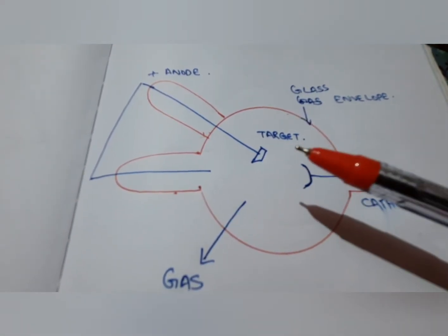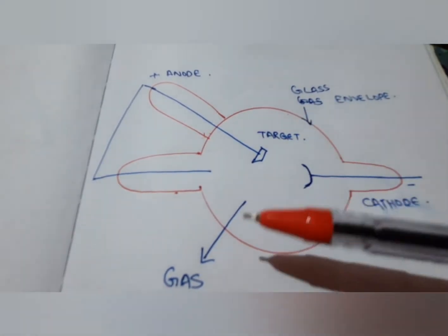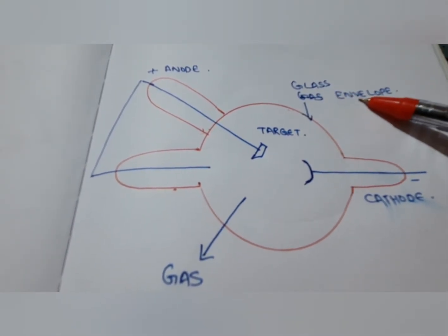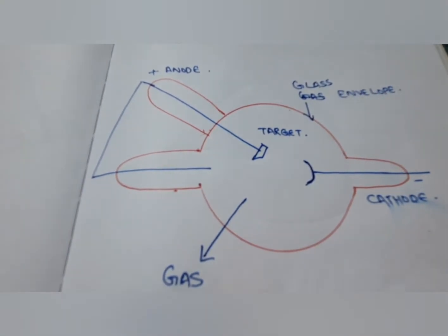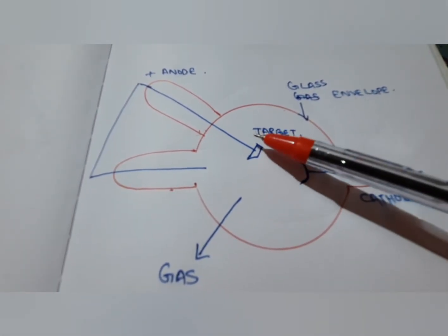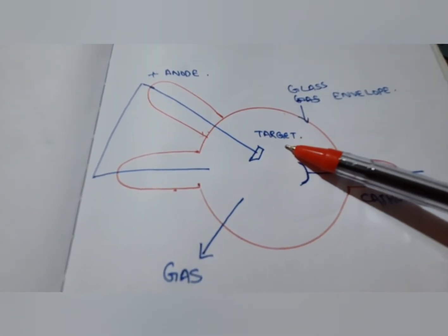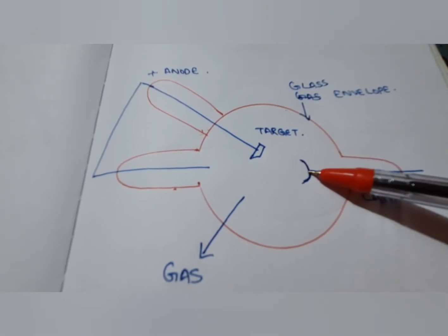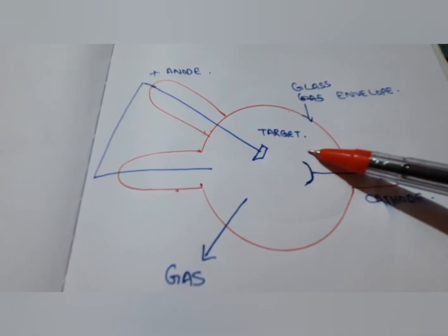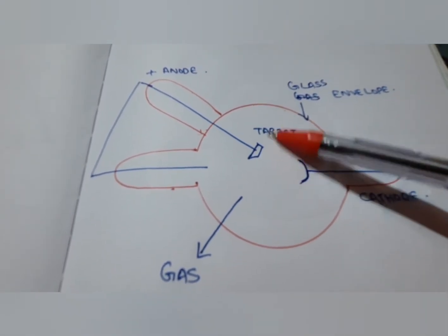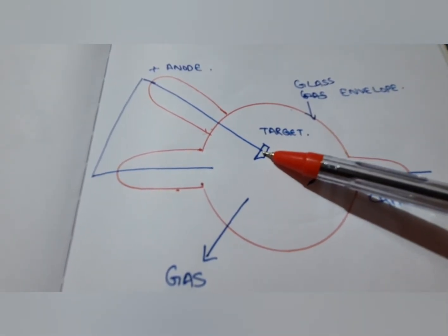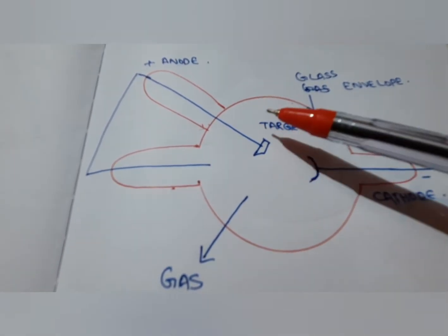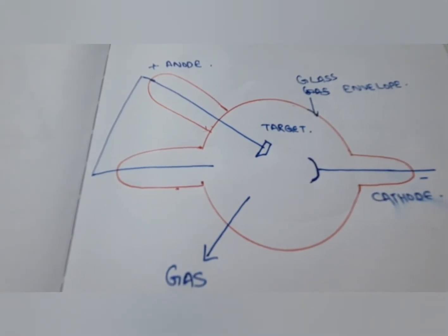This is the gas tube. The entire arrangement inside is placed within a glass envelope filled with gas. It has a positive anode known as the target and a negative cathode. The cathode consists of an aluminium stem and aluminium disc. The target is made up of either tungsten or platinum backed with copper. This is how a gas tube looks.